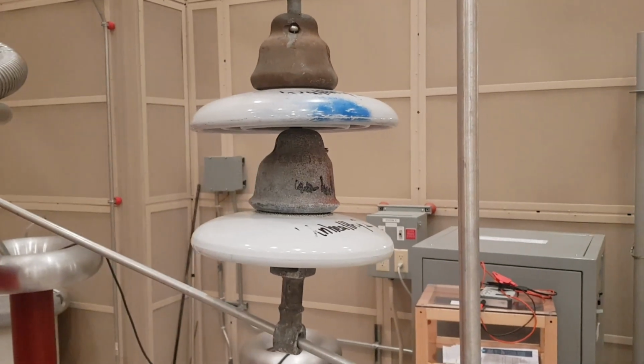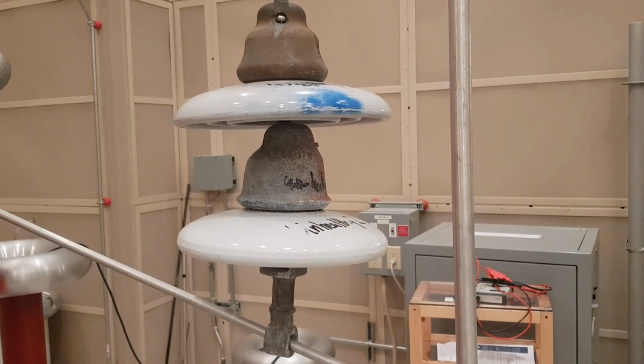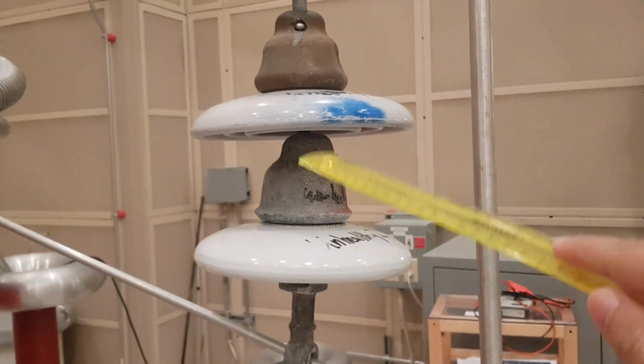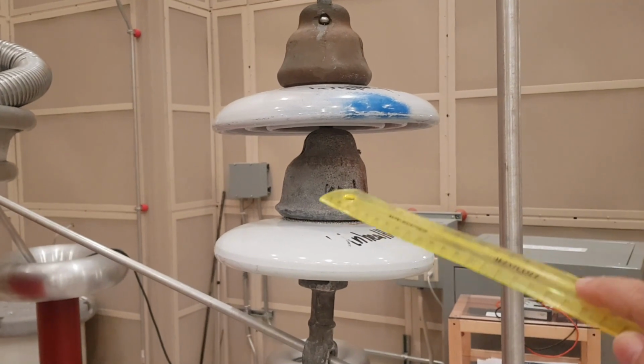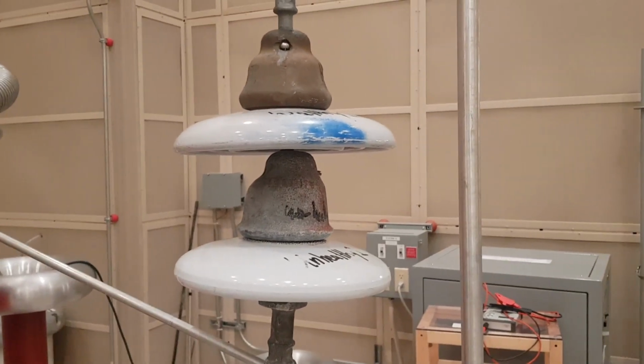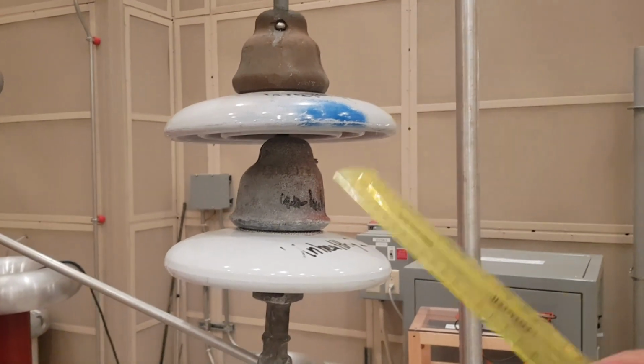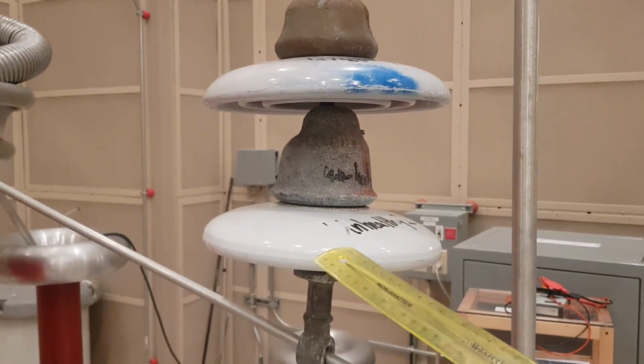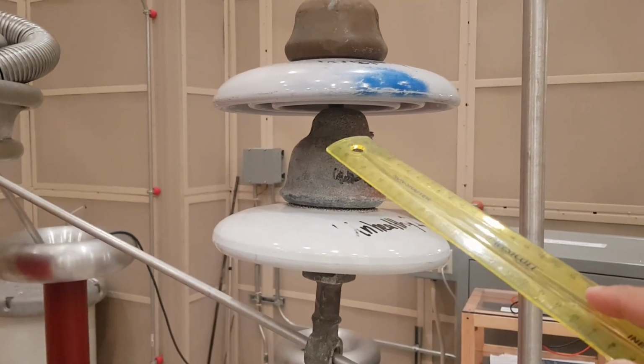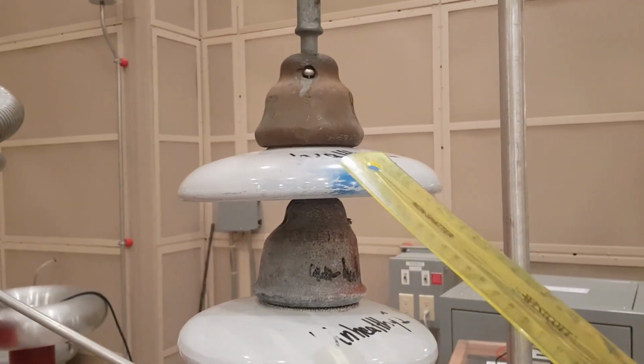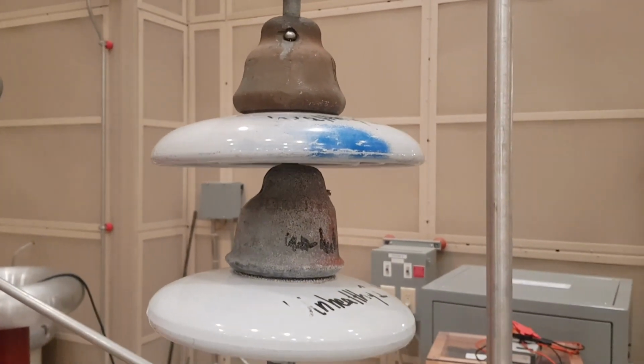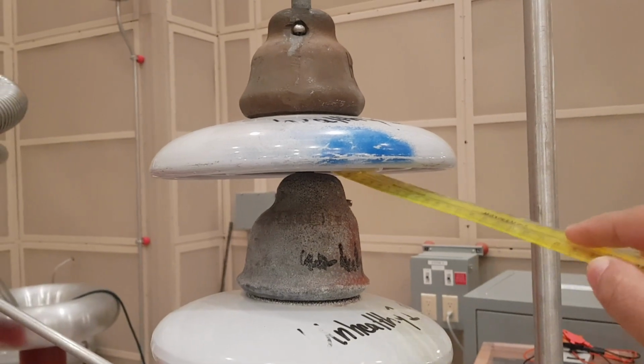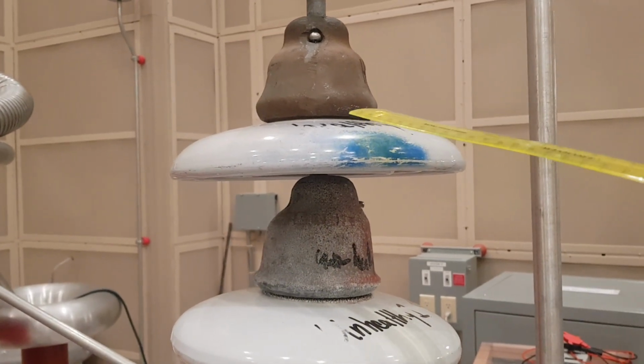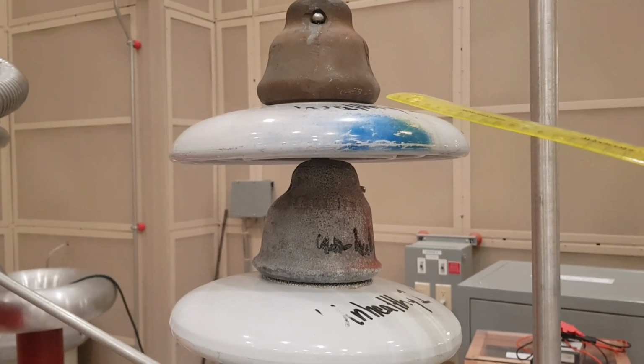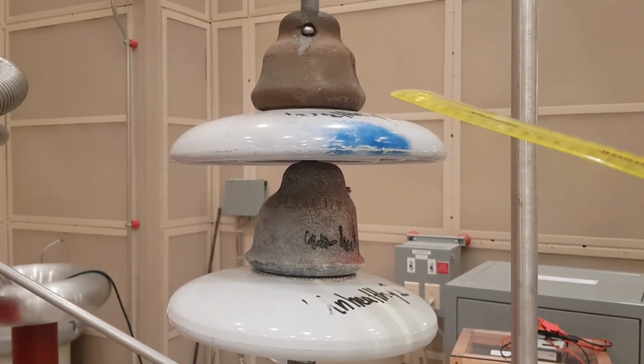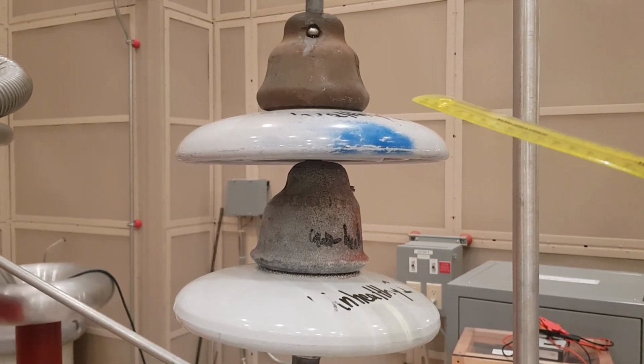Let's explain what happened. When we have two healthy insulators and we apply 30 kilovolt, each disc will share this voltage. So each one will have 15 and 15 kilovolt, and there was no PD activity at all. Now, when the bottom one was unhealthy, and there are some internal discharges inside, the whole 30 kilovolt is now applied across the healthy insulator, and this leads to discharges, as we have seen in the UV camera at the triple point, because of the very high stress here. And the ultrasonic sensor also detected partial discharge from this region.